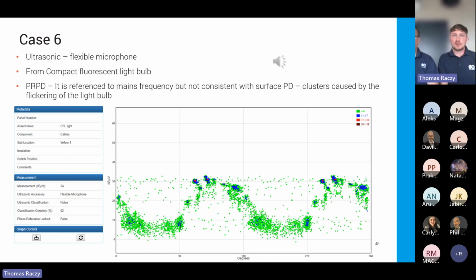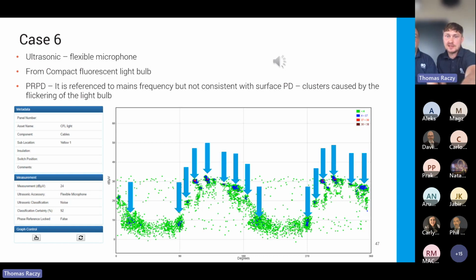Okay, the last case study for today I wanted to present is a case study with the use of a flexible microphone. So it's obviously discharge. Well, it's actually not discharge. This case study shows us the noise from a compact fluorescent light bulb. But the reason why it's so interesting is because you can see it does follow the pattern. So you could almost tell there's a phase resolved pattern there.